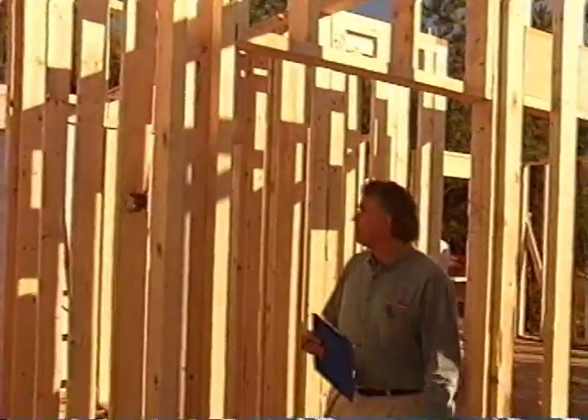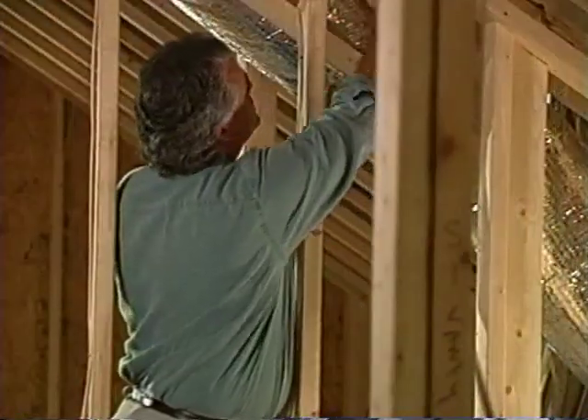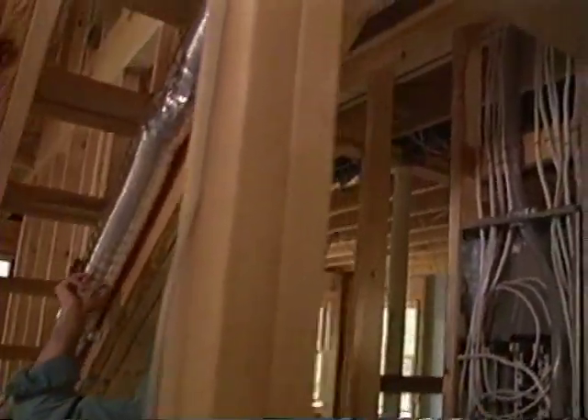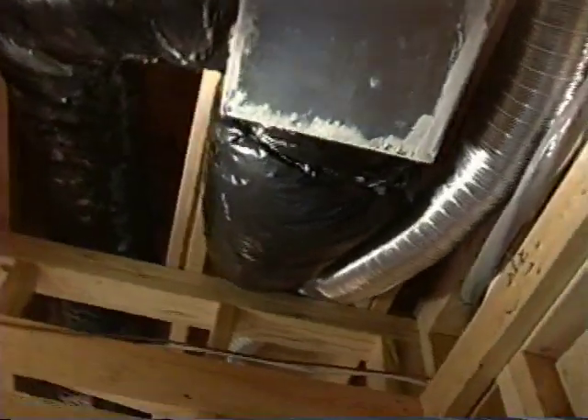Dan McFarland is a building science expert with Advanced Energy Corporation. He sees countless examples of air distribution systems choked off because of improper installation. In this situation, the contractor put his hangers up too high into the joist bays, creating a constriction in the flex duct all along the system wherever there's a hanger. If he had put the hangers a little bit lower, this problem wouldn't have occurred. Whenever we're installing ductwork, whether for heating and air conditioning equipment or for an exhaust appliance, we want to keep ductwork as straight and aligned as possible, because each turn can create restriction in airflow, which has a negative impact on equipment performance.